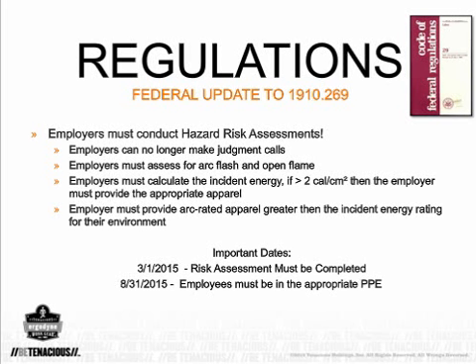In addition to having proper PPE from head to toe, man-made fibers such as nylons and polyesters are no longer acceptable under FR and AR clothing. Only all natural fibers such as 100% cotton, 100% wool, and 100% silk, or FR base layers are allowed. Prior to this change, many employees had the correct outer layer tops. However, their underclothing or bottoms were not FR. Now FR bottoms, outerwear, headwear, and/or gloves may be required for your particular environment. Again, with this change, employers must provide PPE from head to toe.